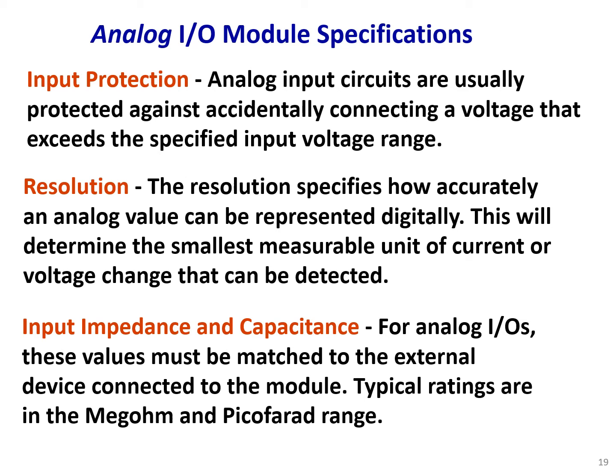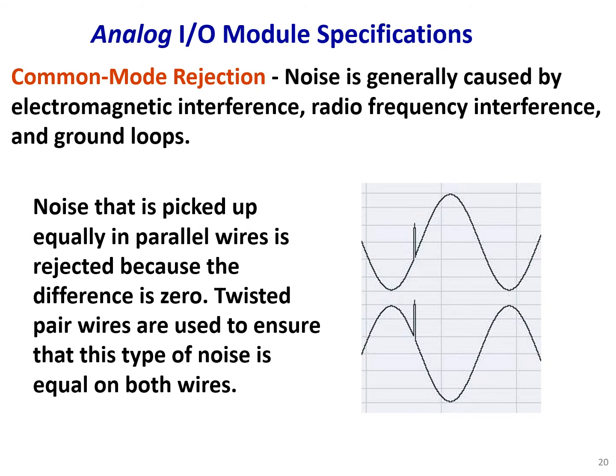Input impedance and capacitance are very important specifications for analog I/Os — these values must be matched to the external device connected to the module. Typical ratings are in the megaohm or picofarad range. Common mode rejection is another specification for analog I/O modules. Noise is generally caused by electromagnetic interference, radio frequency interference, and ground loops. Noise picked up equally on parallel wires is rejected because the difference is zero, and twisted pair wires are used to ensure that this type of noise is equal on both wires, allowing it to be eliminated.